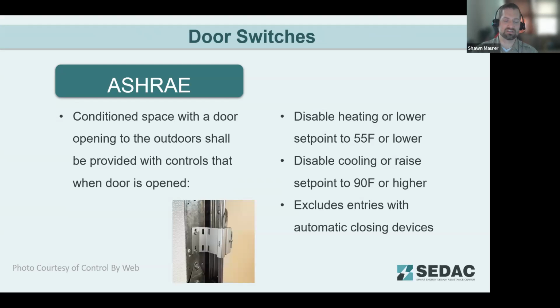For door switches, we touched on this earlier in the simplified requirements section. Here it is in the mandatory requirements in the full section. A conditioned space with a door that opens to the outdoors shall be provided with controls that, when the door is open, either disable the heating or lower the set point to 55 degrees, and disable the cooling or raise that set point to 90 degrees. This excludes entries with automatic closing devices, so your typical vestibule entries.